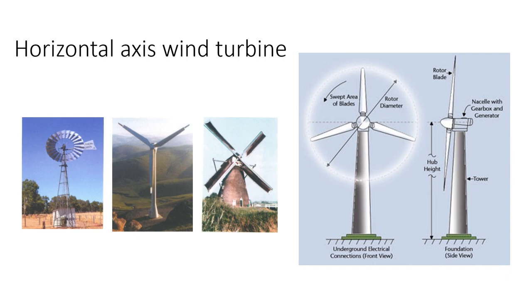Horizontal axis wind turbines, or HAWTs, have the main rotor shaft and electrical generator at the top of the tower and must be pointed into the wind. Small turbines are pointed by a simple wind vane while large turbines use a wind sensor coupled with a servo motor. Most have a gearbox which turns the slow rotation of the blades into a quicker rotation more suitable to drive an electrical generator.